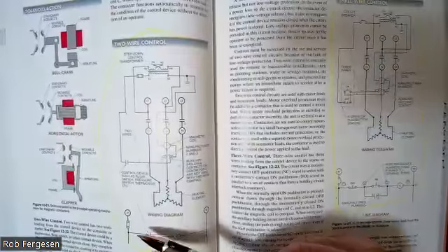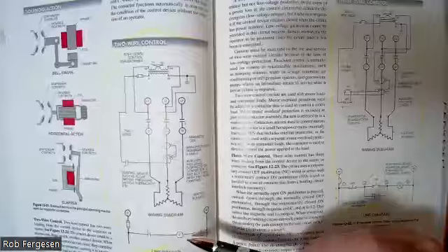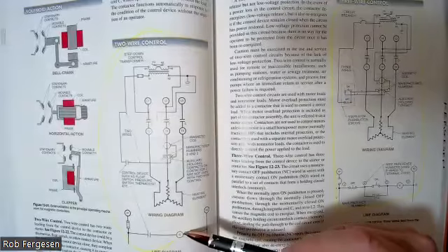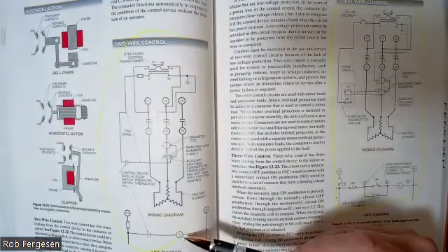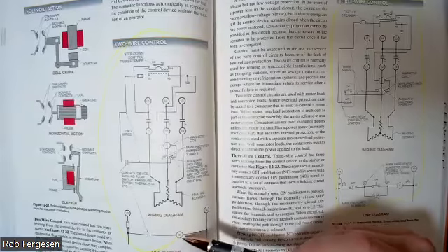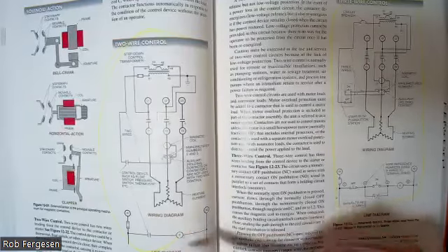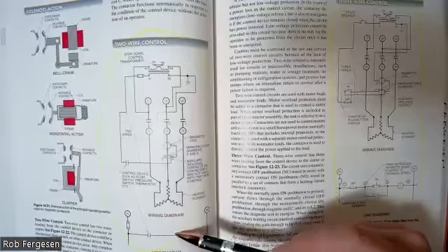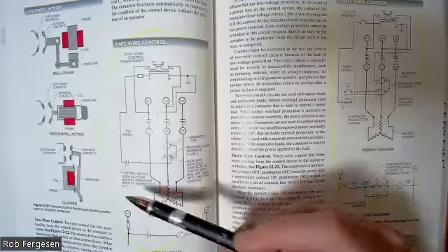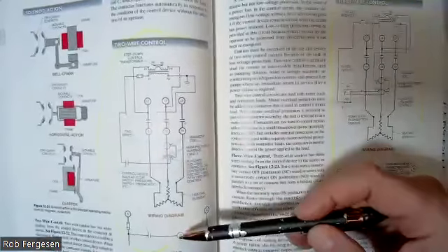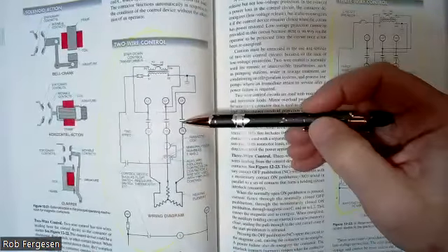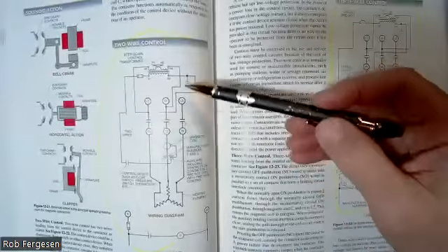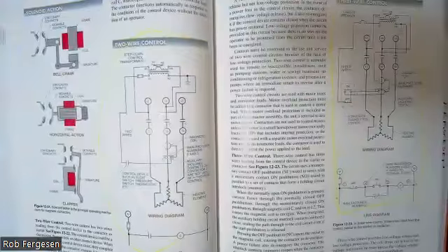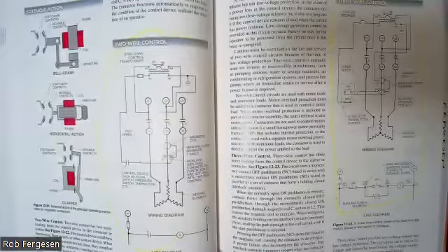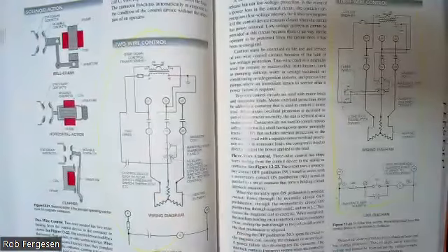some sort of switch. When that switch turns on, it sends power into this. This is the coil. I always see a C on it. I usually see it labeled like coil contactor 1. That C means that I'm energizing the coil that pulls down those contacts and makes them connect. So when I energize that, these get closed and I get power to my device. So this is a really important diagram to understand what all the pieces and parts are.